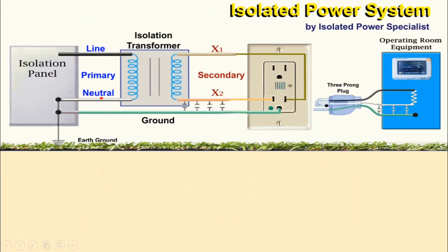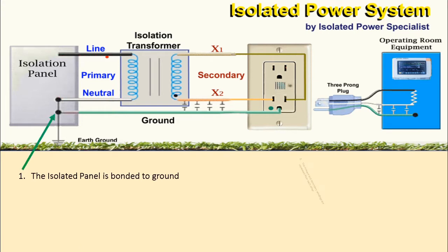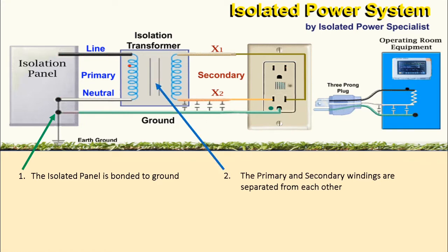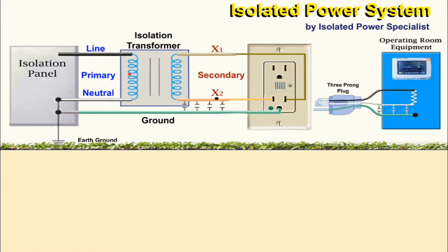Nor are the secondary windings referenced to earth ground. So first, we need an isolation panel to be grounded to earth ground. The second condition is to ensure that the isolation transformer's primary and secondary windings are separated from each other. The primary side shows the line and neutral connections, and this is true since the neutral is grounded to earth ground. However, on the secondary side, neither connection is grounded. Therefore, there is no neutral, so we can't call it line and neutral. We chose to refer to these connections as X1 and X2.